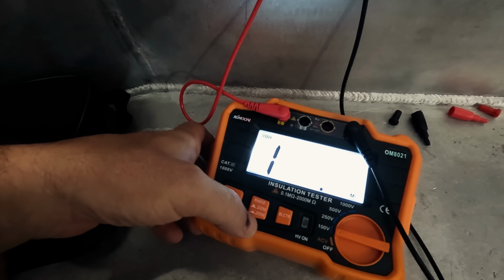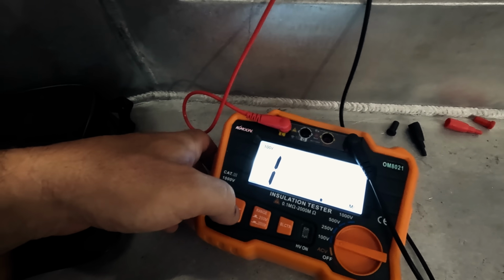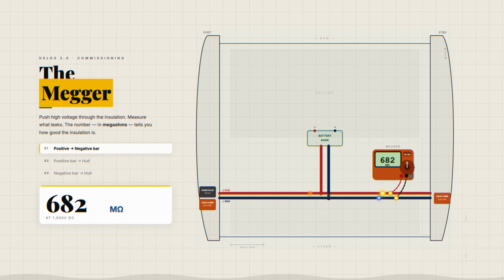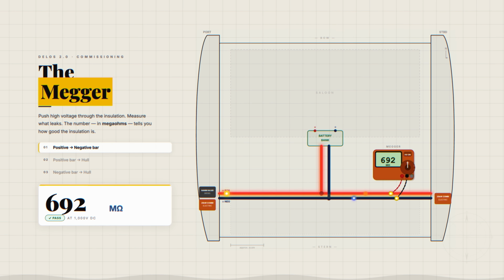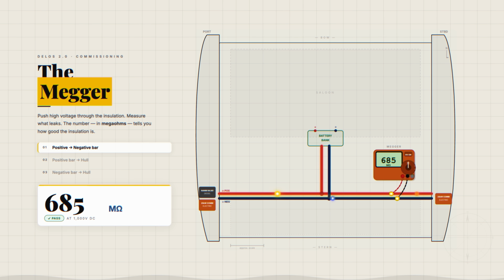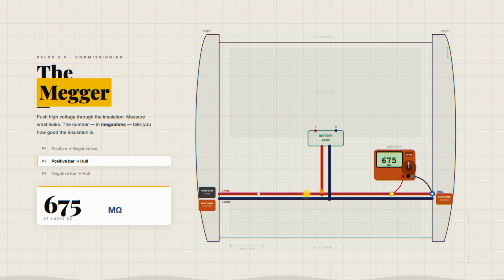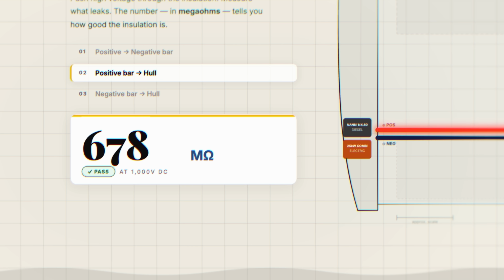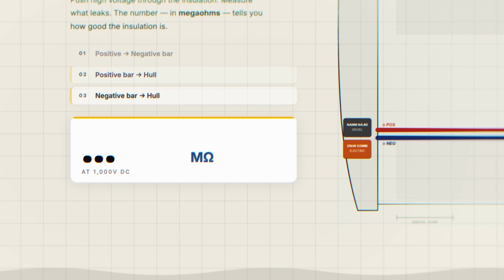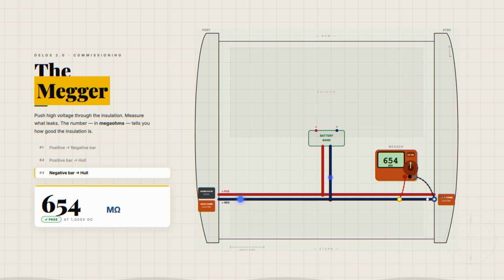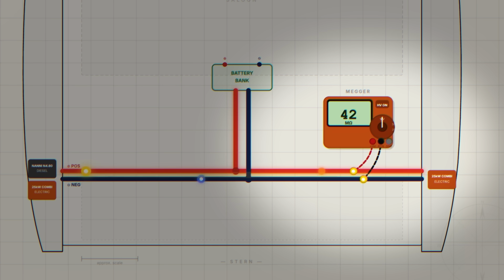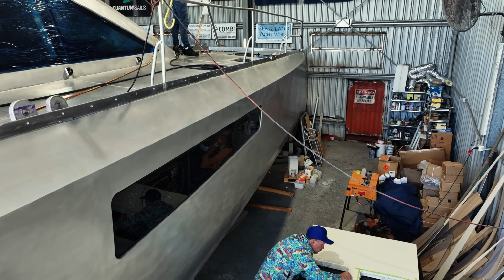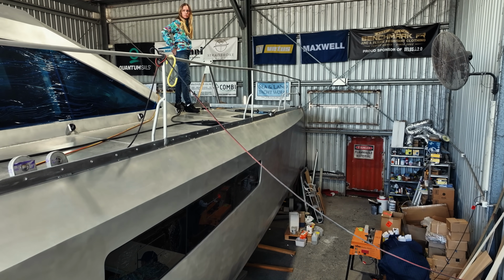We're set at the 200 mega ohm range. The Megger works by pushing a high voltage through a conductor, then measuring if there's any leakage to the other conductor through the insulation. The number it gives you is in mega ohms, a very high measure of resistance, and the higher the better. I need to run 3 tests: positive to negative, positive to the hull, and negative to the hull. All 3 should be completely insulated from each other to pass.